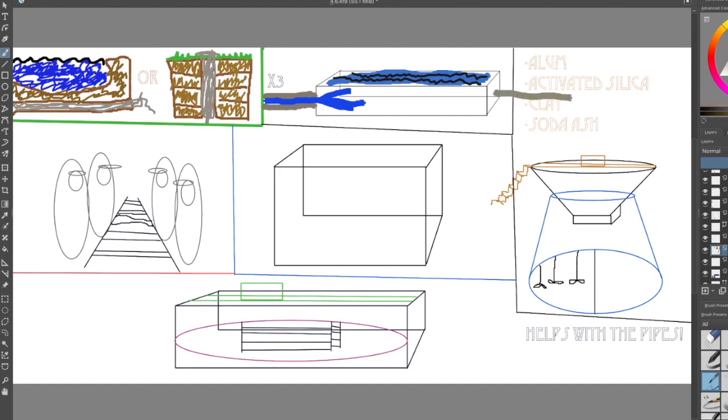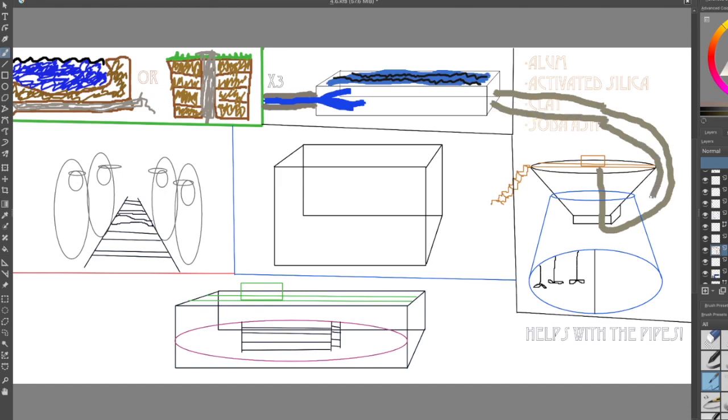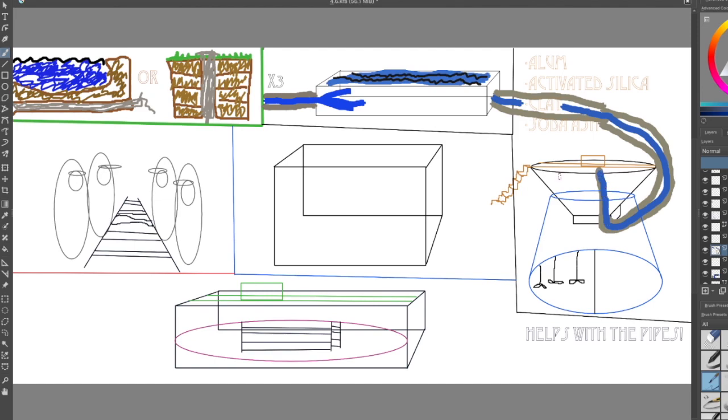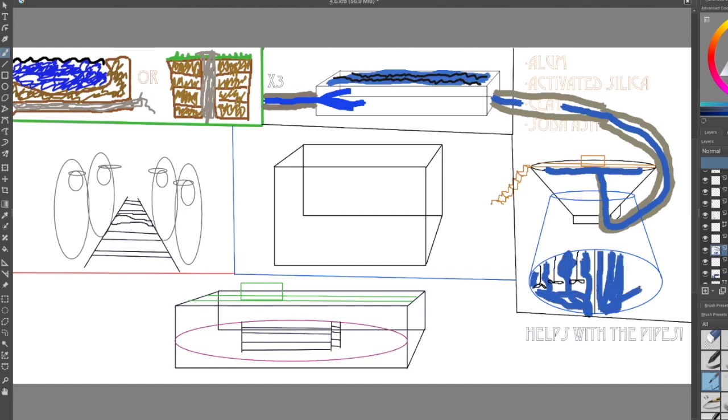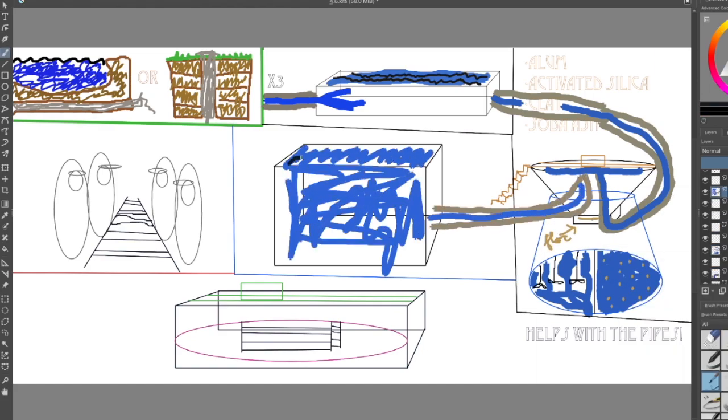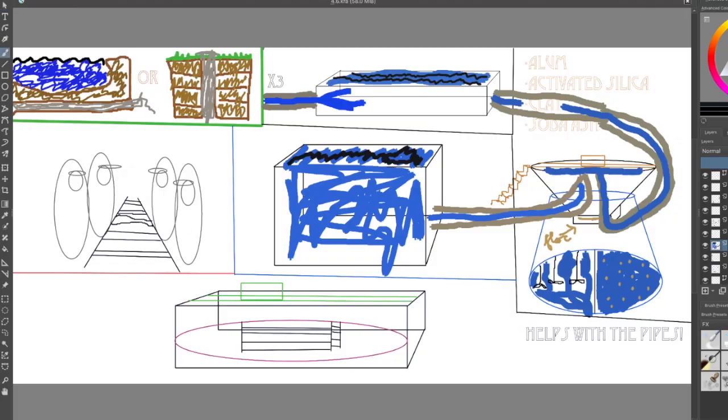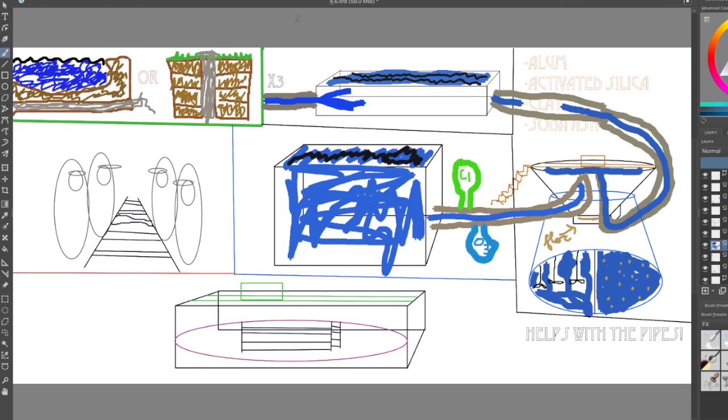Third, the water is pumped into concrete steel sediment basins from 8 to 20 feet deep. In these deep basins, various chemicals are added to the water to suspend even finer matter, including viruses, to form a dense mass at the bottom called floc. The floc is removed every six months. If this step, called flocculation or coagulation, doesn't remove any excessive organic material, then two additional steps called prechlorinating and pre-ozonation will be needed.